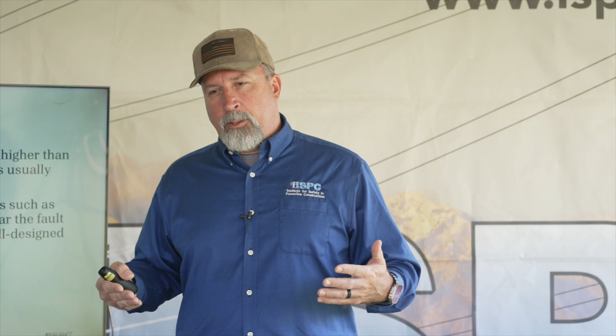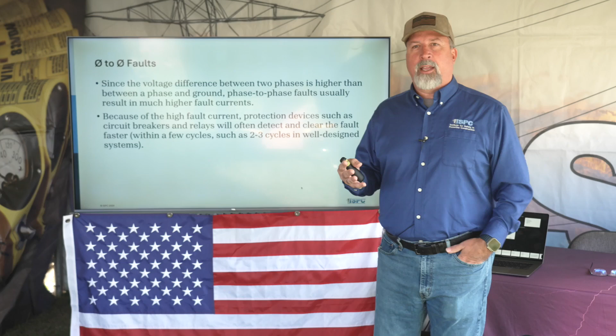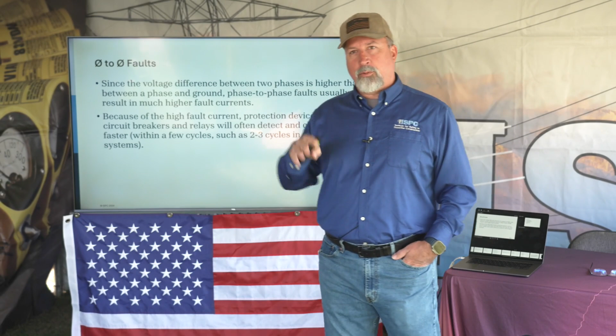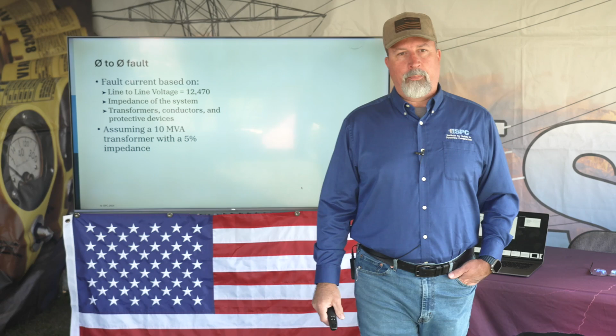The grounding and the bonding, we talk about it, and I think a lot of times the statements get used incorrectly, right? Grounding is not really there to protect you, it's there to protect the system, right? Bonding protects you by eliminating differences in potential. Now you can install your grounds in an equipotential bonded fashion where it's protecting the worker. But really what those grounds are there to do is, one, isolate the fault, whatever it's coming from, induction, accident, re-energization, whatever the case may be. And then the bonding or the equipotential setup is there to hopefully minimize what you as the individual see when it comes to current flowing in that situation, okay? So the quicker we can clear that fault, the better chance we have of not being susceptible to that current flow, okay?